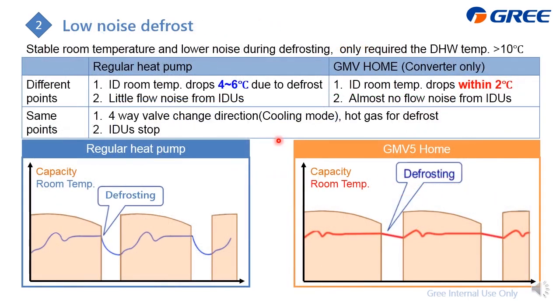Next is the low noise defrost. As we know, the purpose of defrost is just to melt down the ice on the outdoor heat exchanger. For that, we need to perform cooling, right? At that time, we need to send the hot gas to the outdoor unit, and after it absorbs heat, which melts down the ice, the refrigerant will become liquid. Then we can send this liquid for the GMV home. We can send it to the domestic hot water. If it is higher than 10 degrees, then we can absorb the heat, which makes the refrigerant become gas and flow back to the compressor.